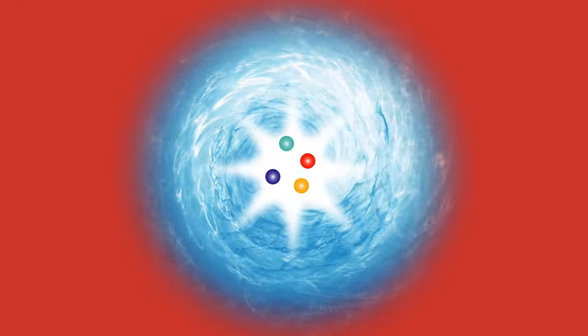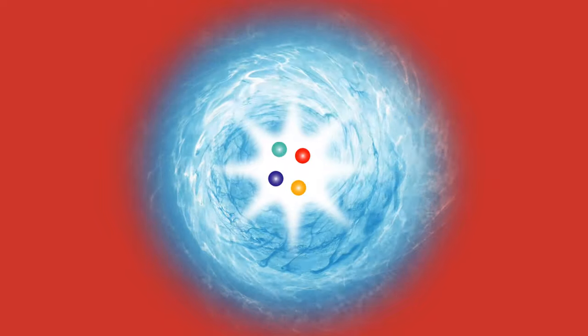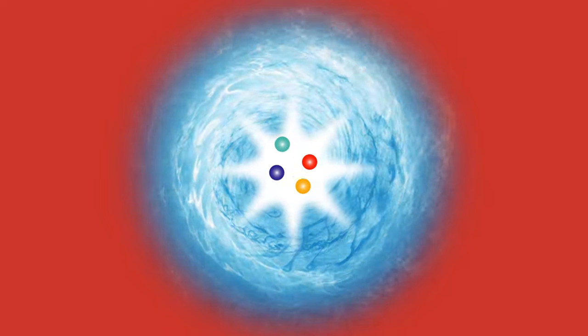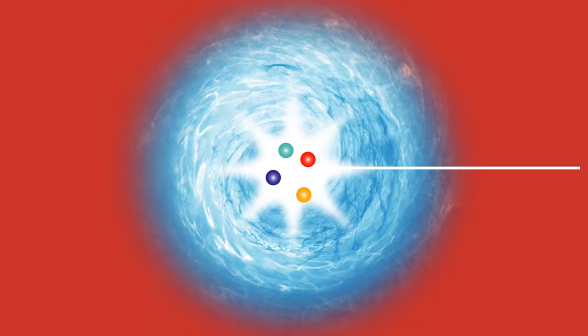To find out exactly what chemical elements are in a liquid sample, the analyzer runs it through an extremely hot plasma. As the heat excites the atoms and ions of the sample elements, they emit light.